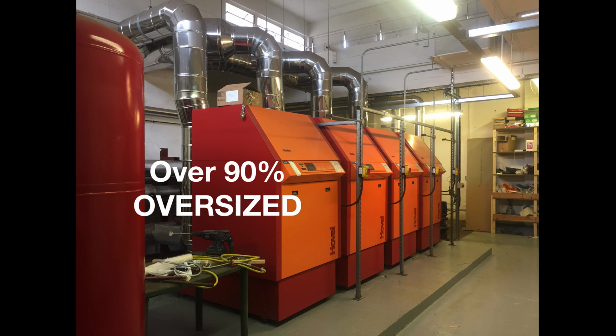The actual figure required for this unit, including the hot water and a diversity factor, was 2.3 megawatts. So you can just imagine what the savings would be on plant costs alone of upgrading scenarios like this. Not that these need upgrading, but that's the point, and this is where you can save clients vast sums of money.